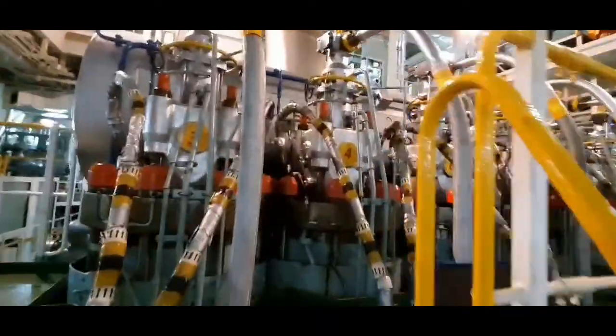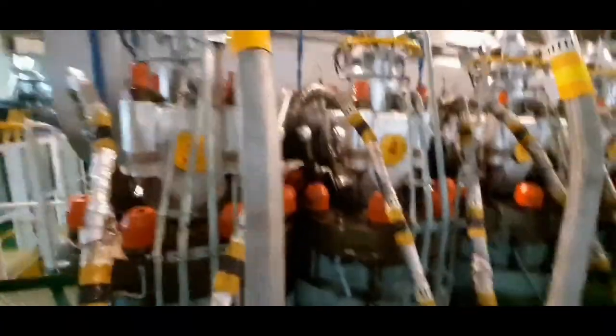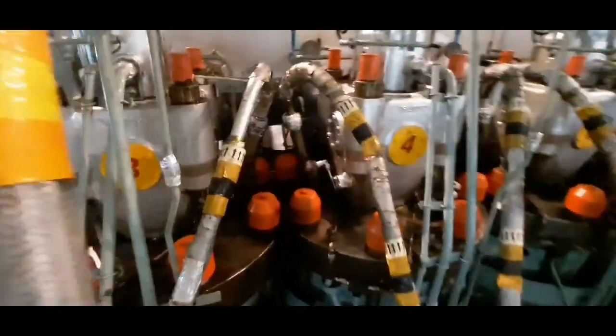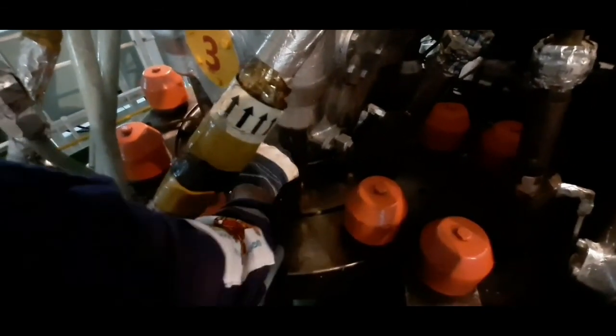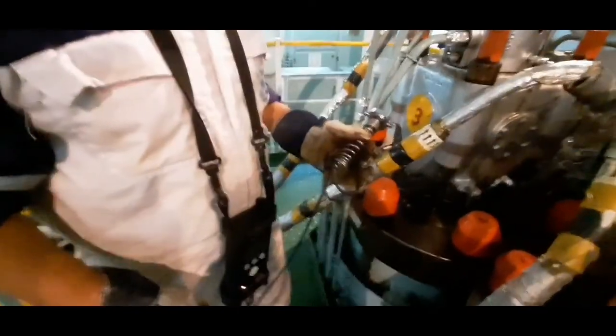Friends, before mounting the transducer on the indicator cocks, make sure you always blow through the carbon deposits inside the gas passage on the indicator cocks. This is done in order to prevent any damage to the sensor inside the transducer. After you carry out the blow through, connect the transducer on the indicator cocks.